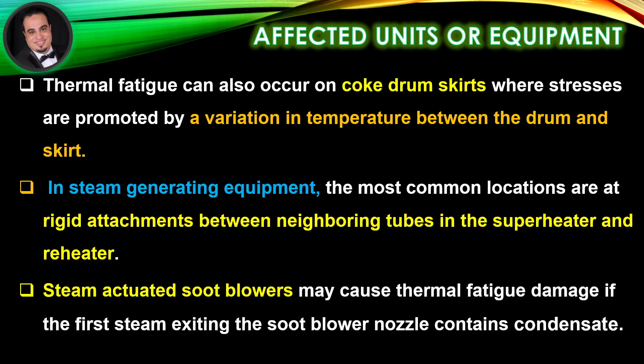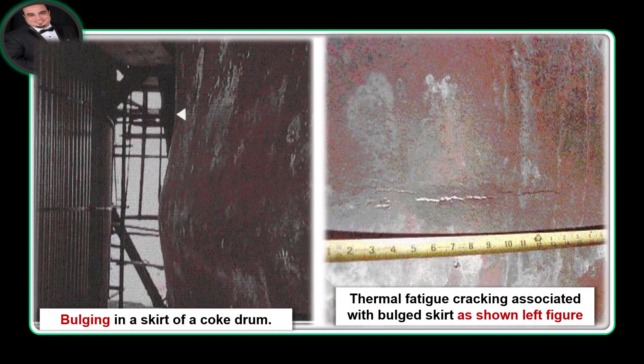Thermal fatigue can also occur on coke drum skirts where stresses are promoted by a variation in temperature between the drum and skirt. In steam generating equipment, the most common locations are at rigid attachments between neighboring tubes in the superheater and reheater. Steam-actuated soot blowers may cause thermal fatigue damage if the first steam exiting the soot blower nozzle contains condensate. Figures illustrate bulging in a skirt of a coke drum due to thermal cycling and associated thermal fatigue cracking.